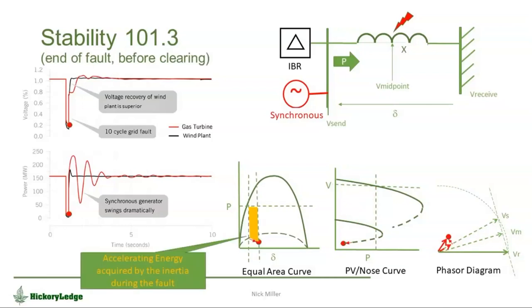The next slide here is at the end of that disturbance. Again, all familiar to you, right? The voltage has further sagged as we've sucked some of the flux out of the machine. The system now has pulled apart. The sending end voltage phasor has moved out, but it's still deeply depressed. And the orange hashed in space is the energy that that inertia, which in this case is not really our friend, has accumulated in the course of the fault and needs to dissipate. We all know that. And let's clear the fault.